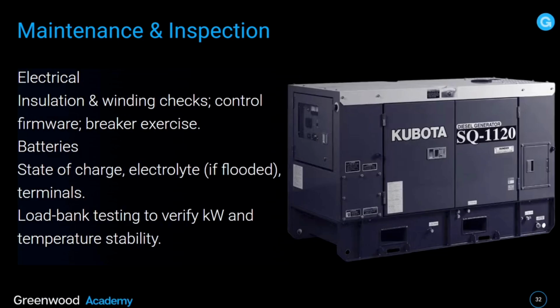Very important. Still under the maintenance and inspection, you're looking at electrical, so insulation and winding checks, control firmware, breaker exercise, batteries, the state of charge, electrolyte if flooded, terminals, load bank testing to verify kilowatt and temperature stability.